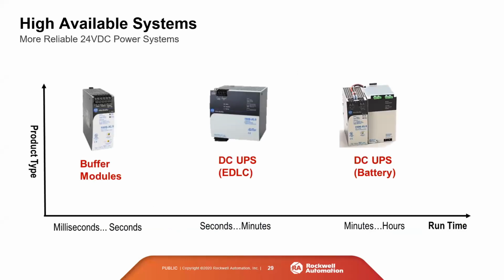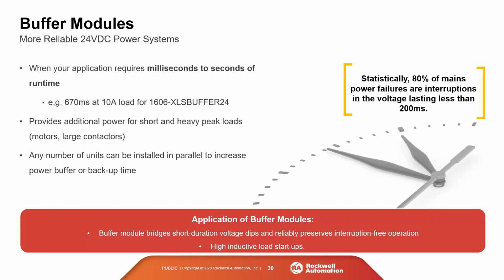On the left, you see our buffer module providing milliseconds to seconds. Our DC UPS, EDLC, which is electrolytic dual layer capacitor, provides seconds to minutes, and then our longest runtime, minutes to hours, is our DC UPS with the battery. Like I said, statistically, 80% of main power failures are interruptions in voltage that last less than 200 milliseconds. Short failures aren't going to matter for non-sensitive loads like your light bulbs, but they can cause electronic equipment to drop out completely.